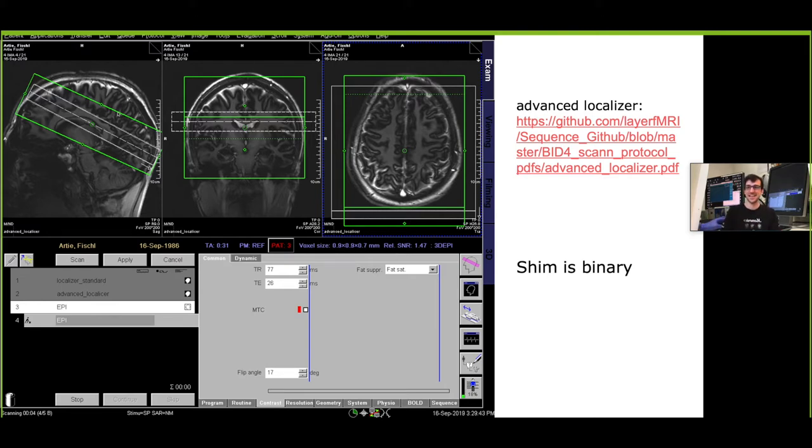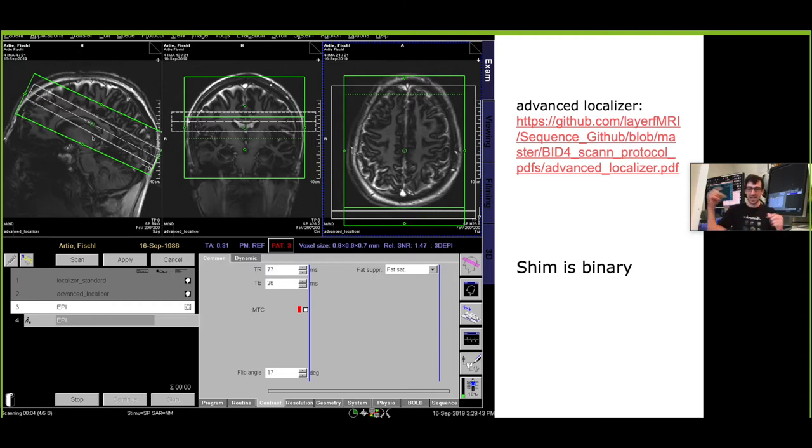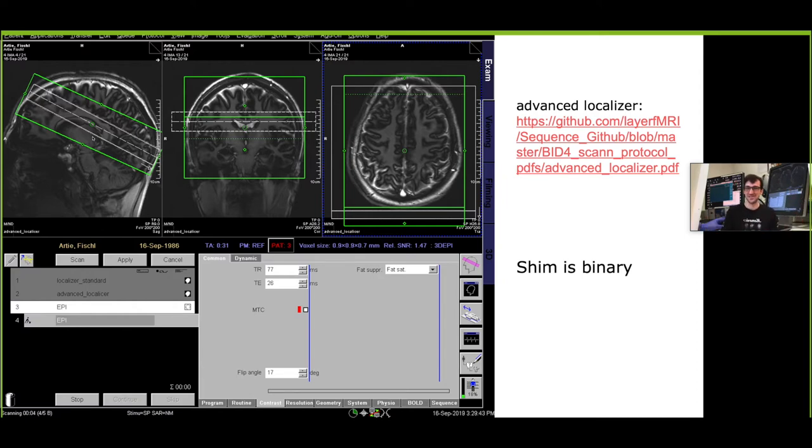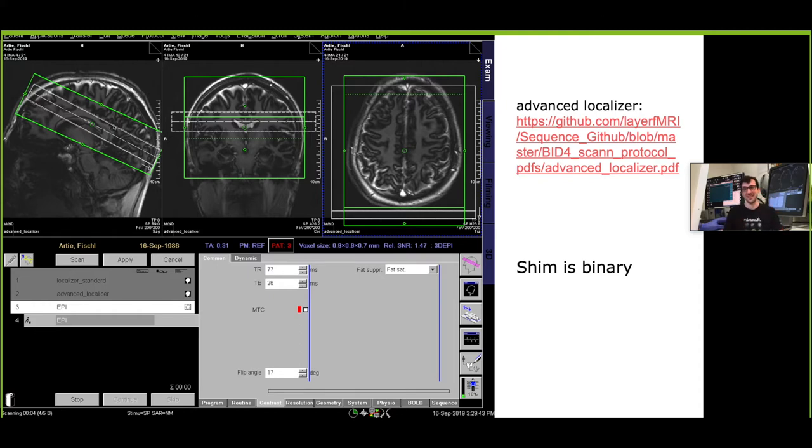Usually the three rules about shimming that I follow when doing layer dependent fMRI is that I make the shim box a bit bigger than my thin slab. This is partly due to the fact that the field maps that are used in order to calculate the shim currents are usually not that high resolution, so you cannot easily fit a higher order spherical harmonic to just two or three voxels of the field map.